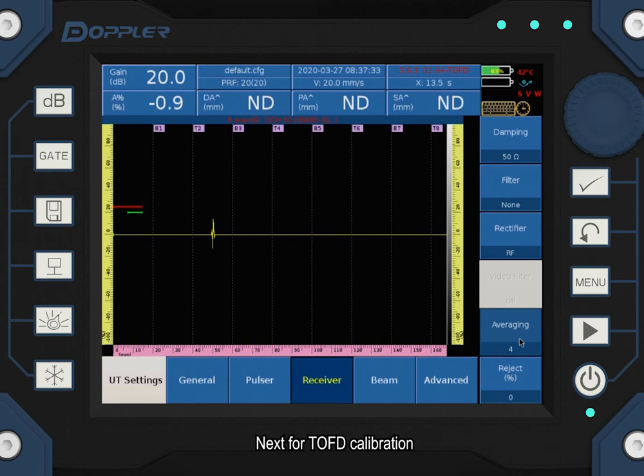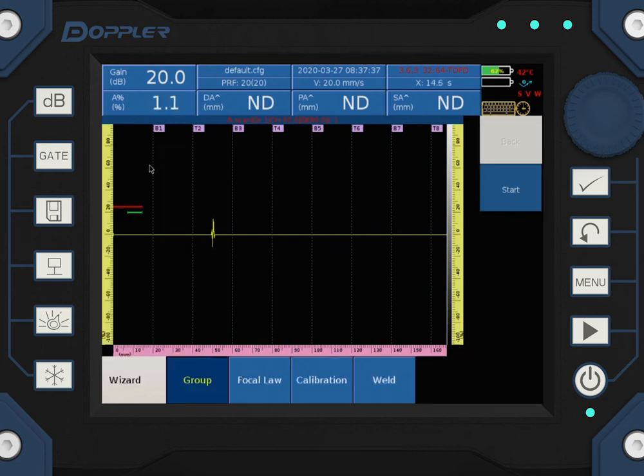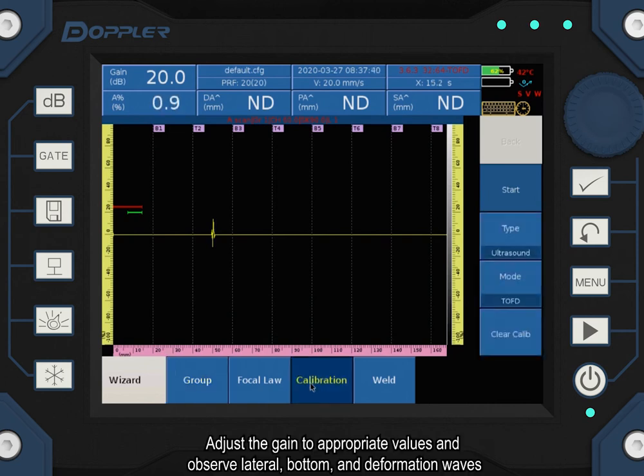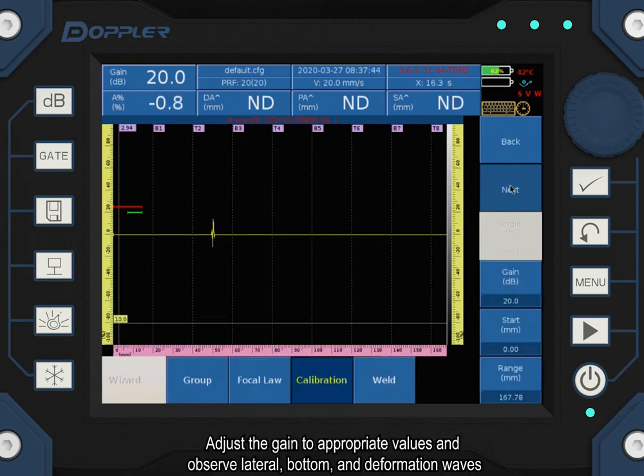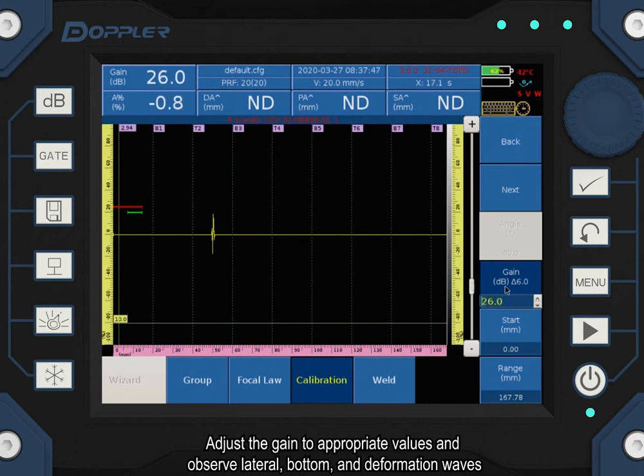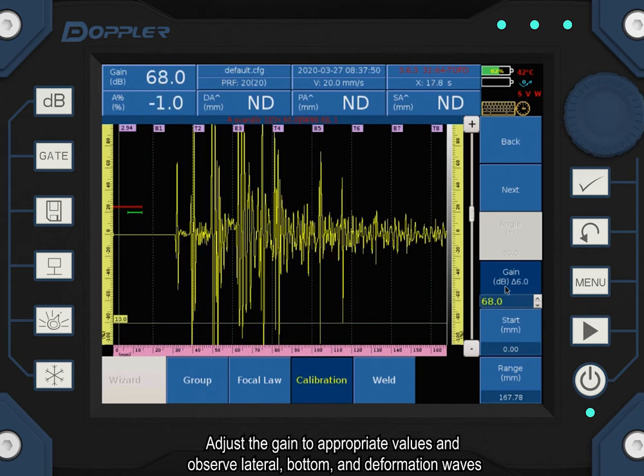Next, for TOFD calibration. Adjust the gain to appropriate values and observe lateral, bottom, and deformation waves.